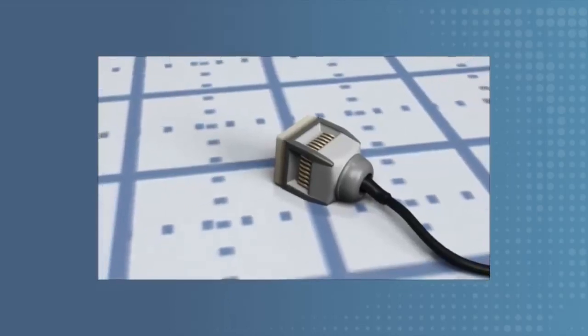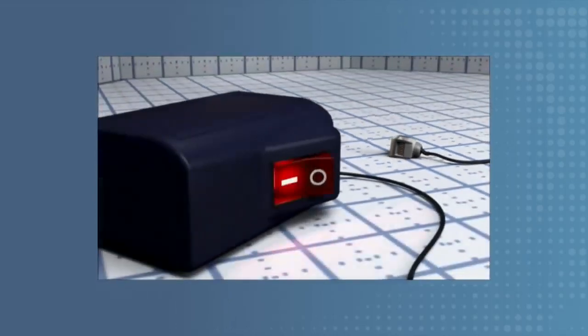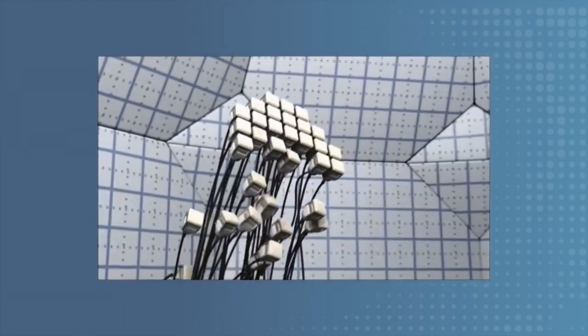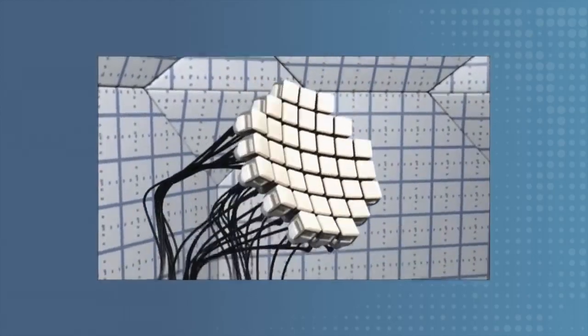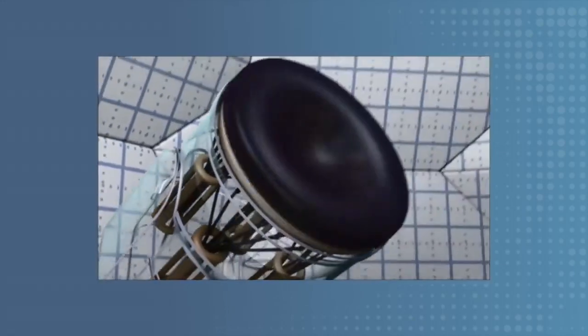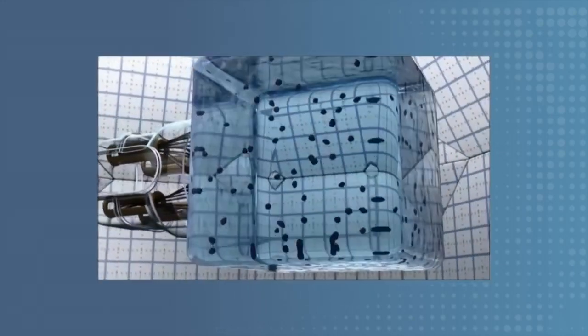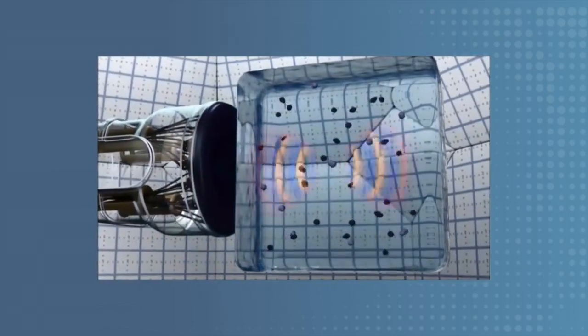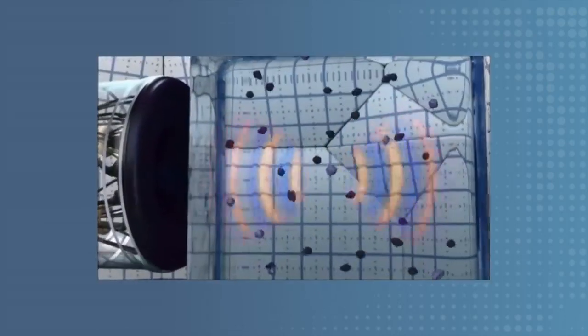And the most important component of that is the ultrasonic transducer. And the fundamental part of the ultrasonic transducer is the piezoelectric element. This, when electricity is applied to it, vibrates. And those vibrations then create an ultrasonic wave that can propagate through tissue. Now, by arranging an array of these elements in a concave formation, the transducer then becomes capable of transmitting ultrasonic waves that then increase sharply in strength at the focus. By pulsing those waves, we create the histotripsy effect to destroy tissue at the cellular level.